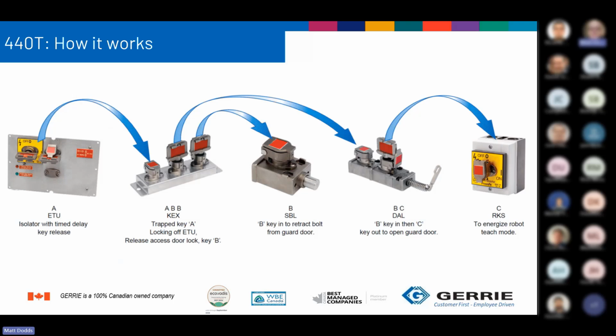So how does it work? On the right hand, or left hand side of the screen here, depending on where you look, you see an isolator. This has a time delay release key. So what I do is I have one non-removable key, marked in yellow there. I turn that key and it then starts the timing sequence. So the key on the right is trapped until the timing sequence ends, and then a solenoid releases that key. I can then turn it.